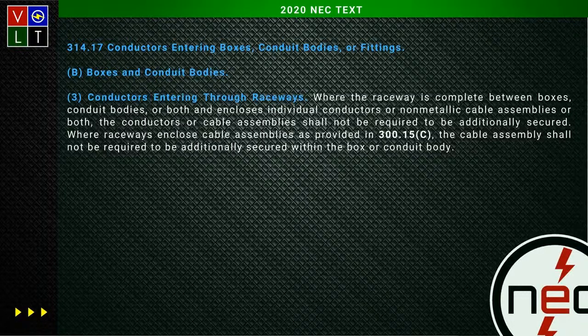Right, yes you can. Somebody brought up heat dissipation, but you've got to remember, when they're running that non-metallic sheathed cable in there, most of the time it's not being fully loaded, and it's less than 10% of the run, which I believe is referenced somewhere around 310. It says that if the run is less than 10%, it's not required to be ambient temperature adjusted.